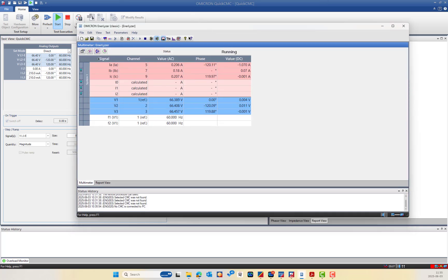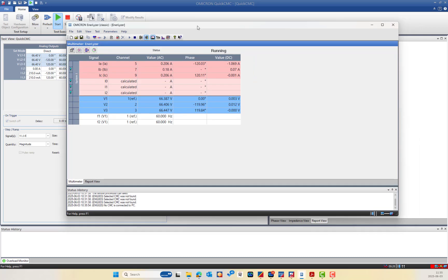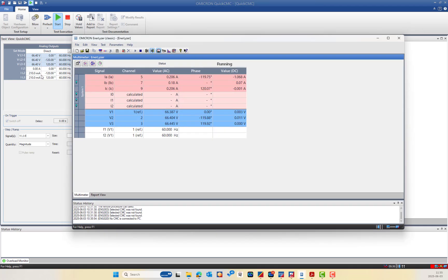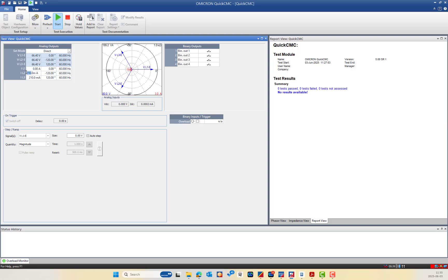I am injecting only 210 mA in phase B. The current clamp at 100 mV/A measures it correctly with an angle of -120°, but the C-Shunt 1 milli-ohm shows the weak signal error icon. This confirms that the C-Probe current clamp is very suitable for lower current injection. You can also increase to 1A.